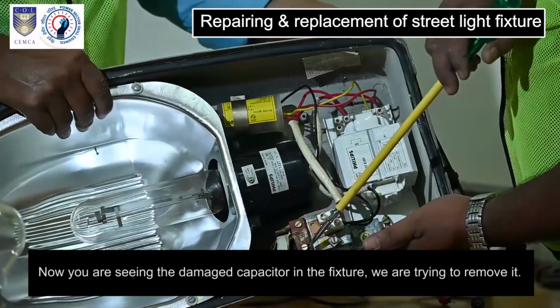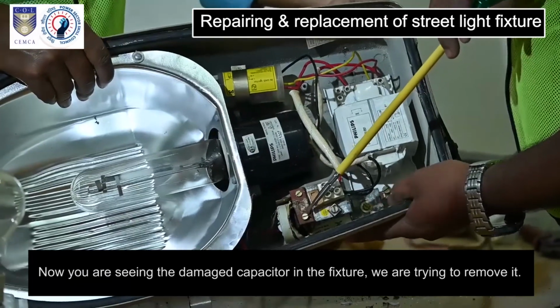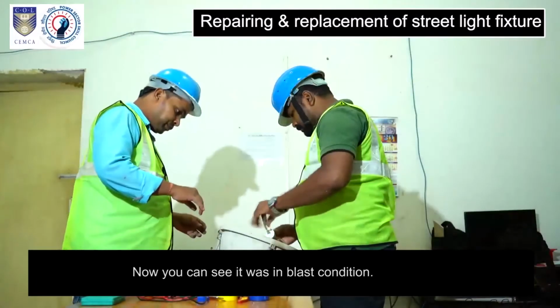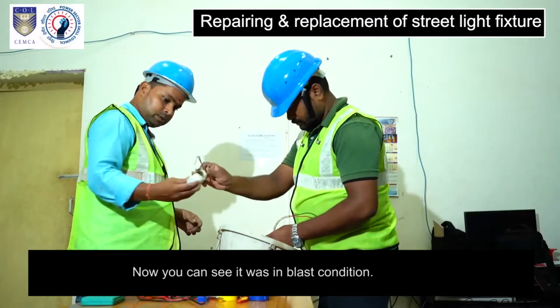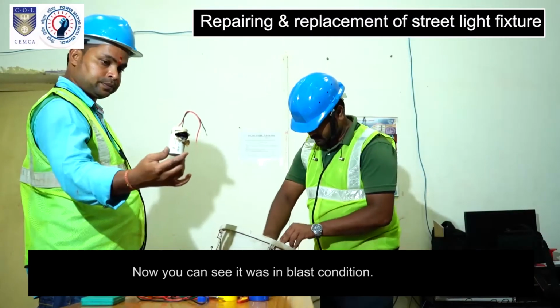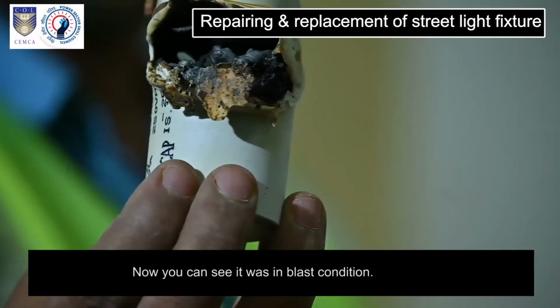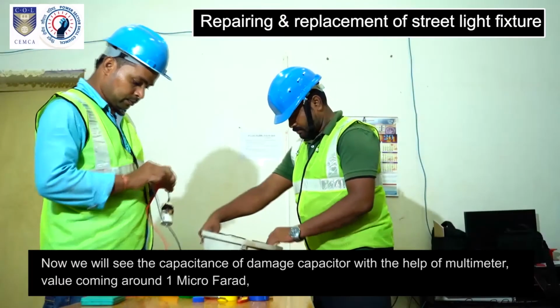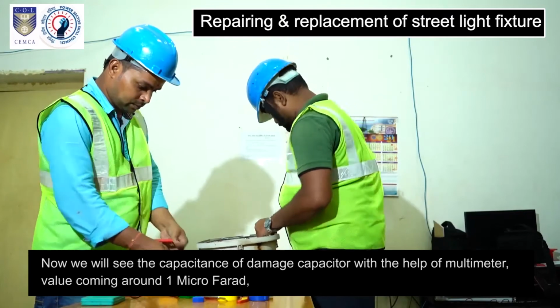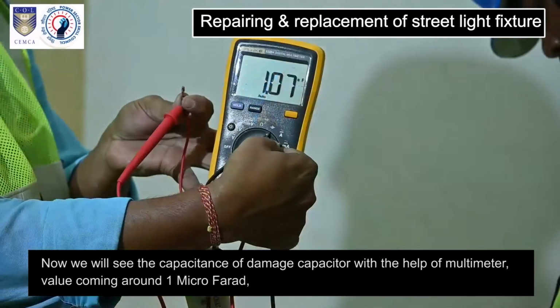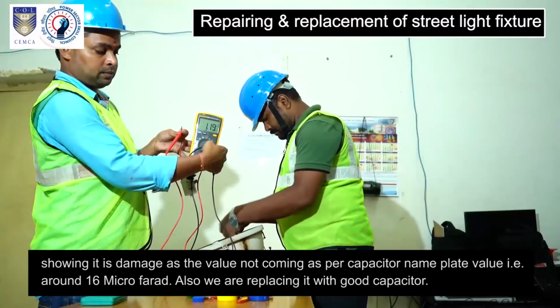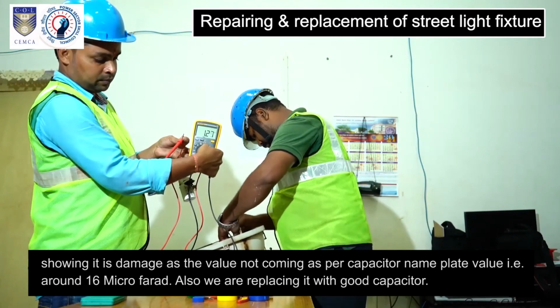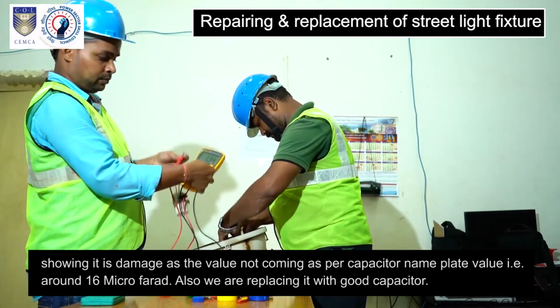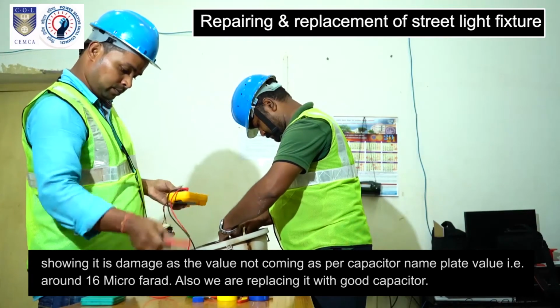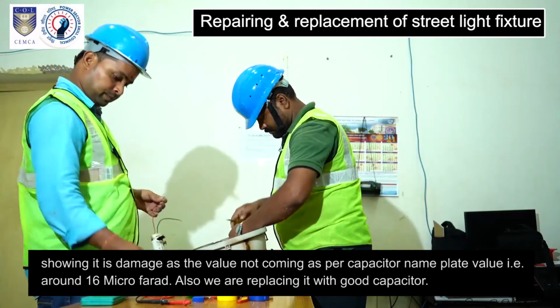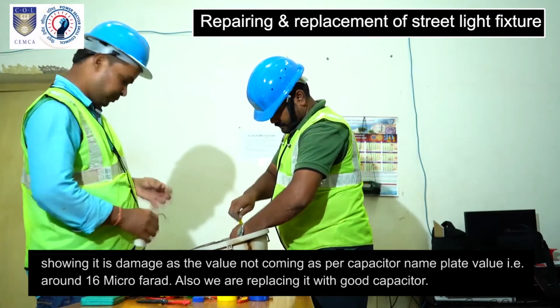Now you are seeing the damaged capacitor in the fixture. We are trying to remove it. Now you can see it was in blast condition. Now we will see the capacitance of the damaged capacitor with the help of the multimeter. The value is coming around 1 microfarad, showing it is damaged, as the value is not as per the capacitor nameplate value, which is around 16 microfarad. Also we are replacing it with a good capacitor.